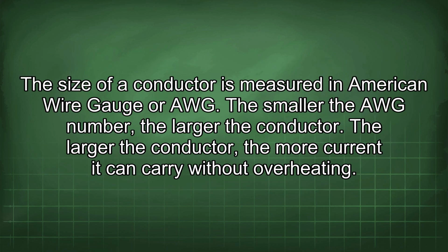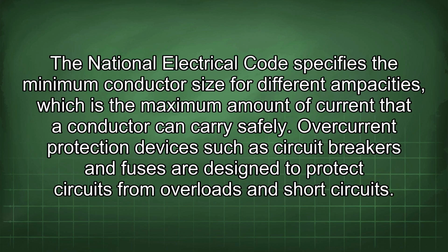The size of a conductor is measured in American wire gauge, or AWG. The smaller the AWG number, the larger the conductor. The larger the conductor, the more current it can carry without overheating. The National Electrical Code specifies the minimum conductor size for different ampacities, which is the maximum amount of current that a conductor can carry safely. Overcurrent protection devices such as circuit breakers and fuses are designed to protect circuits from overloads and short circuits.